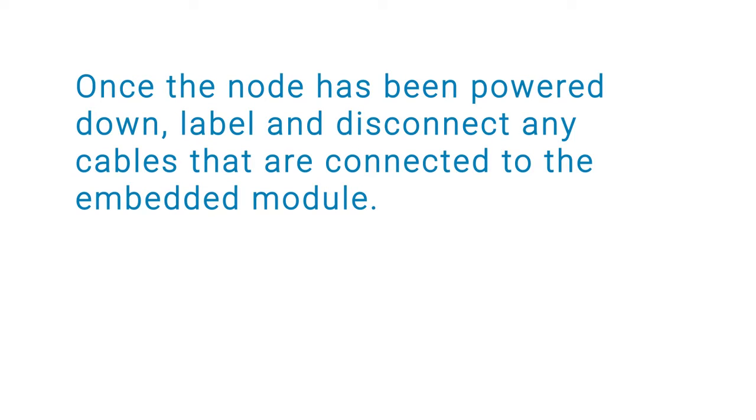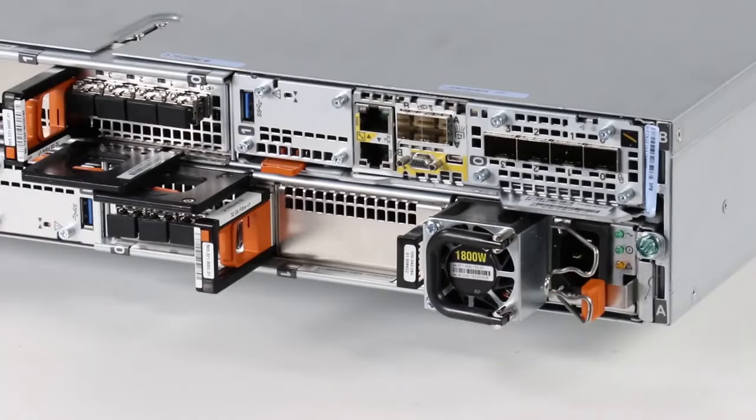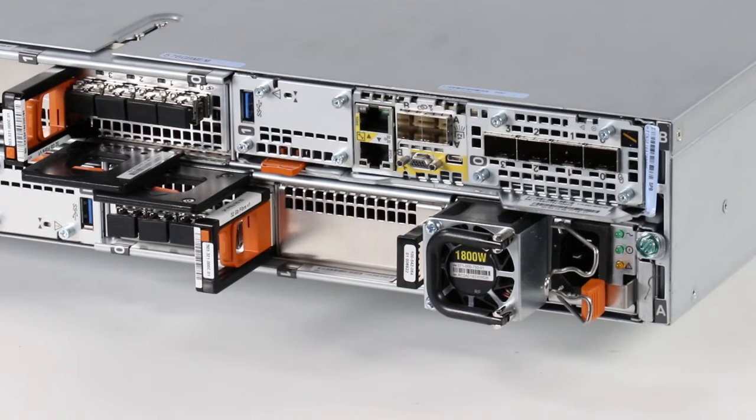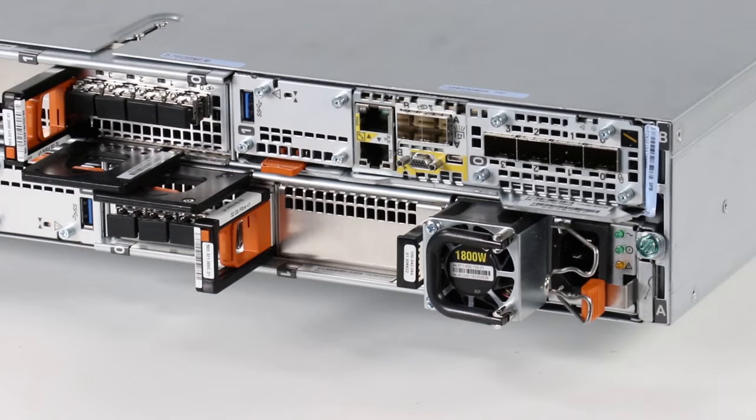Once the node has been powered down, label and disconnect any cables that are attached to the embedded module. The 4 port card is located within the PowerStore embedded module, so you must remove the embedded module to access it.